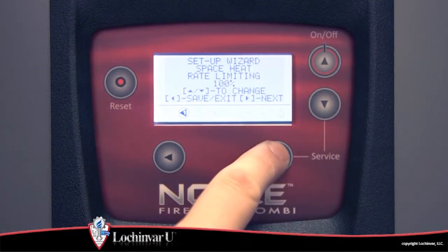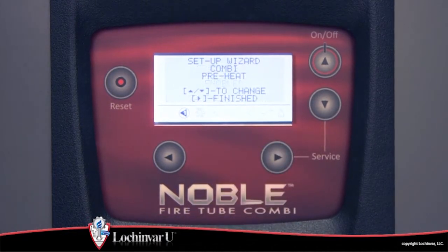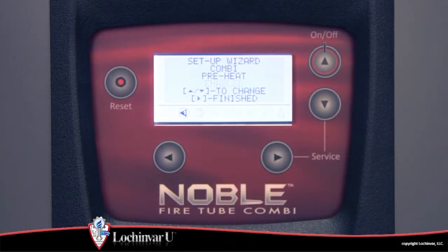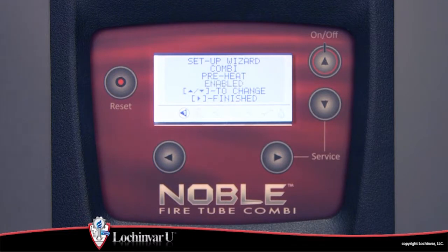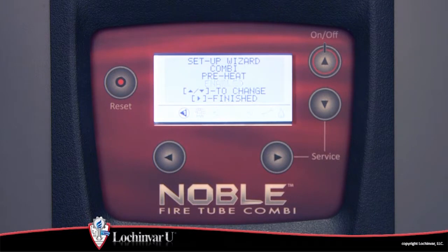The tenth parameter visible is combi pre-heat. This feature can improve the domestic hot water performance of the unit by maintaining the boiler water temperature at an elevated level to be able to immediately serve a domestic hot water demand by keeping the heat exchanger hot.